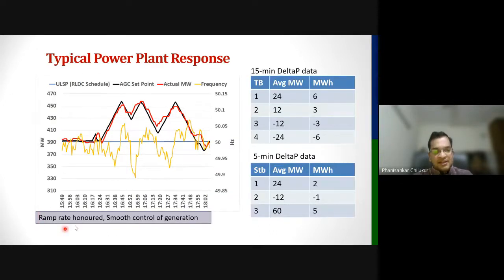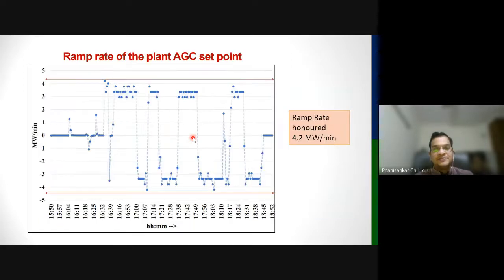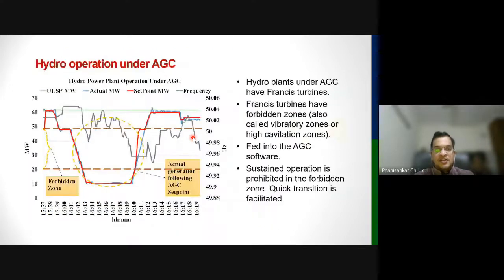So while AGC controls the power plant, the typical power plant is something like this. Typical power plant response. The black is the AGC set point. Red is the actual megawatt. So when the power plant is under remote, the red should always follow black, the AGC set point, to a large extent. While doing so, see, all these instructions are in ramps. Because we honor the ramp rate and we want to do a smooth control of generation instead of steps, power system always does ramp limited control. Okay. Like I said, we honor the ramp rate of the power plant.